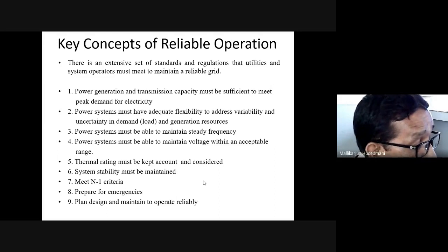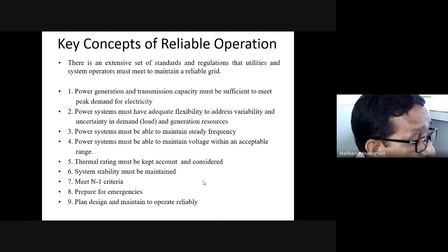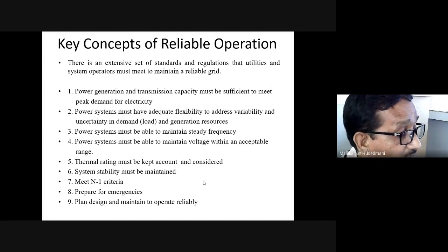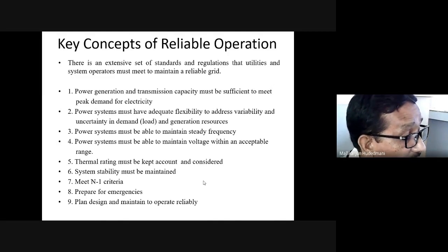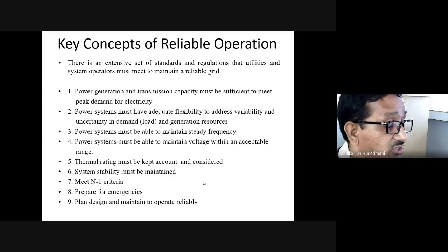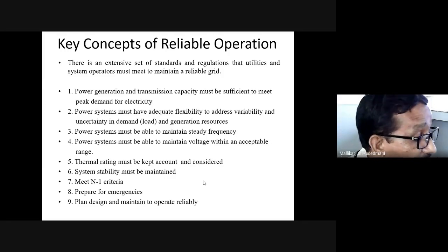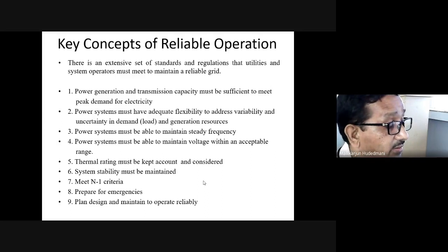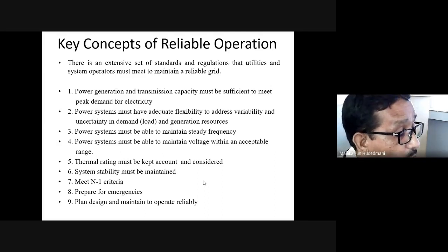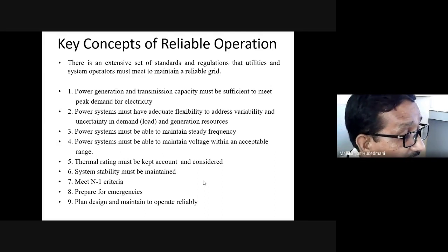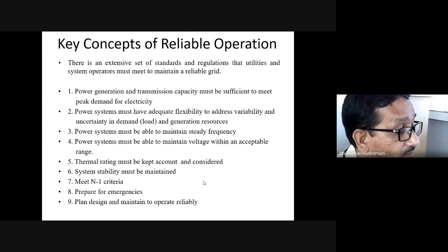Therefore, the thermal rating of every connected piece of equipment must be considered. I gave the example of a transmission line. Why not a transformer? Why not a generator? All the connected equipment must be appropriately monitored with their thermal rating considered. It shall not be simply overridden. Else, the other overriding factors will dominate.